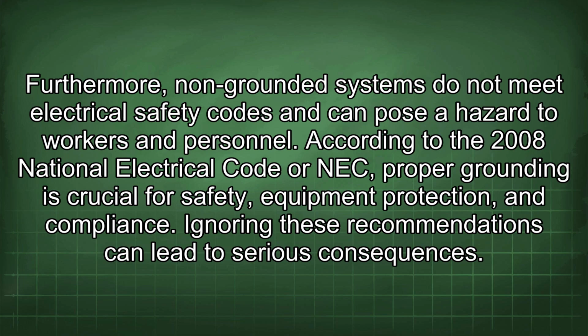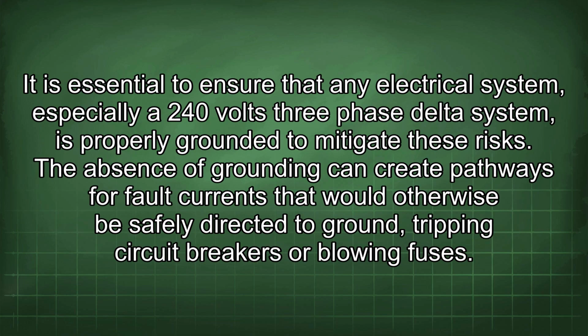According to the 2008 National Electrical Code, or NEC, proper grounding is crucial for safety, equipment protection, and compliance. Ignoring these recommendations can lead to serious consequences. It is essential to ensure that any electrical system, especially a 240 volts three-phase delta system, is properly grounded to mitigate these risks.